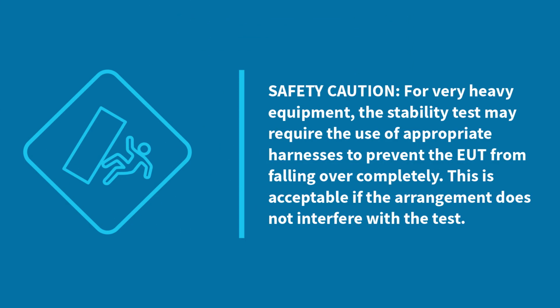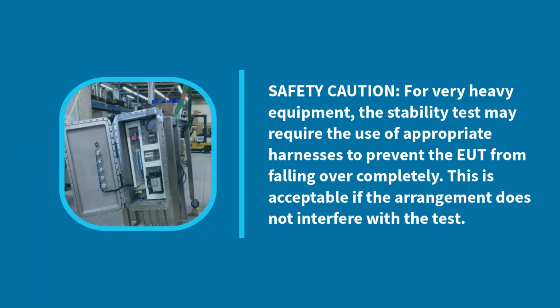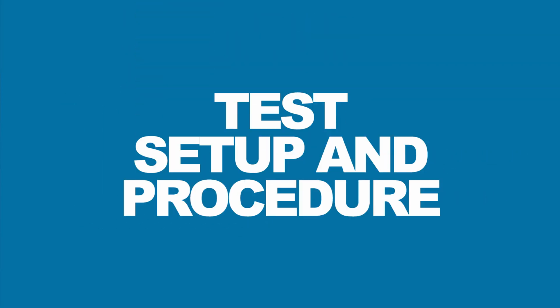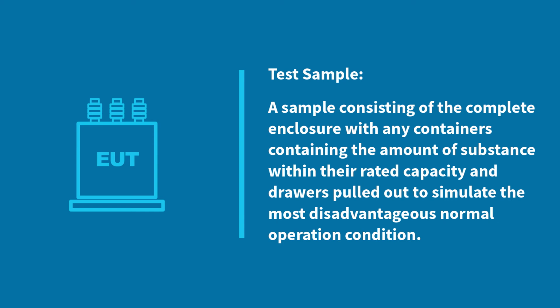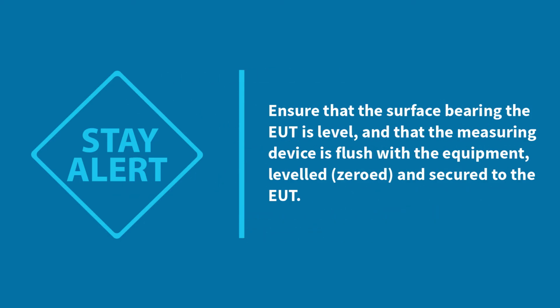Safety caution. For very heavy equipment, the stability test may require the use of appropriate harnesses to prevent the EUT from falling over completely. This is acceptable if the arrangement does not interfere with the test. Test setup and procedure. Test sample. A sample consisting of the complete enclosure with any containers containing the amount of substance within their rated capacity and drawers pulled out to simulate the most disadvantageous normal operation condition. Ensure that the surface bearing the EUT is level and that the measuring device is flush with the equipment, leveled, zeroed, and secured to the EUT.